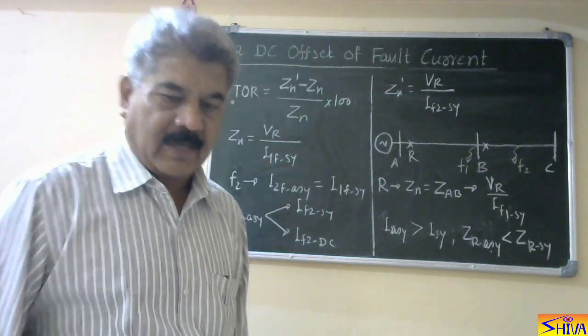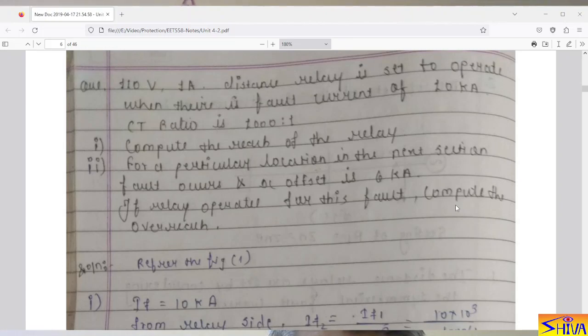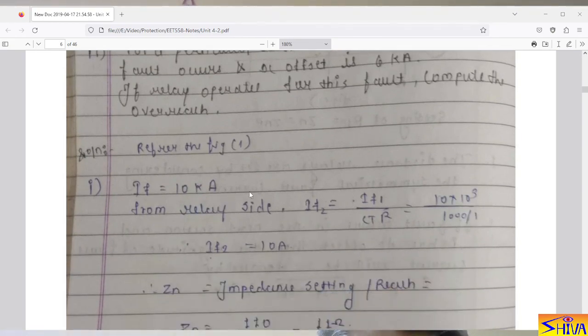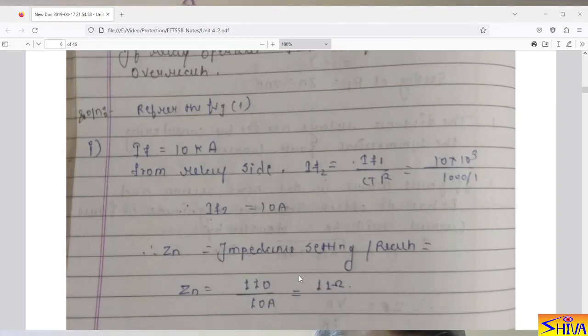I will take one numerical to explain this factor. A 110 V, 1 A distance relay is set to operate when there is a fault current of 10 kilo-amperes. CT ratio is 1000:1. First part: compute the reach of the relay. The impedance setting is Vr upon Ir, which is 110 divided by 10, giving 11 ohms. So the reach of the relay ZN is 11 ohms.